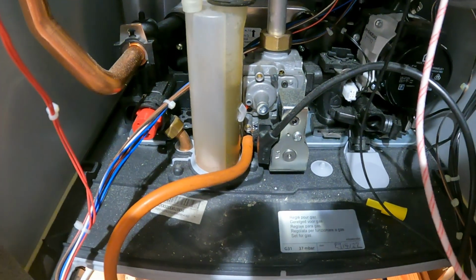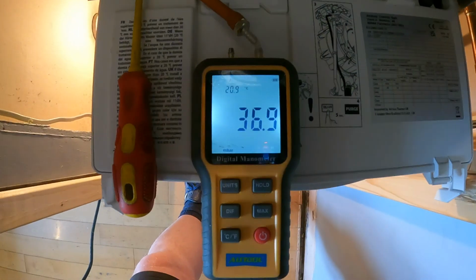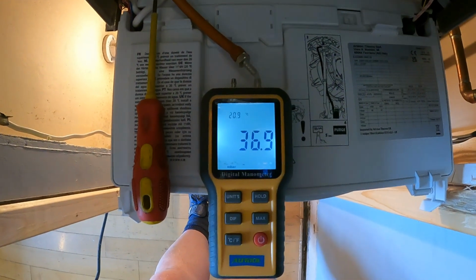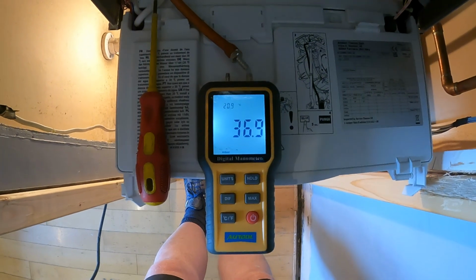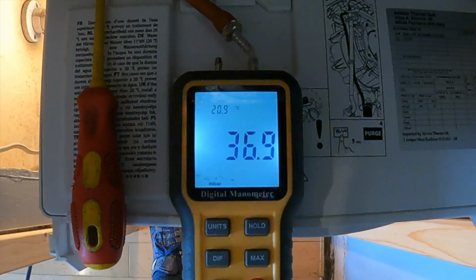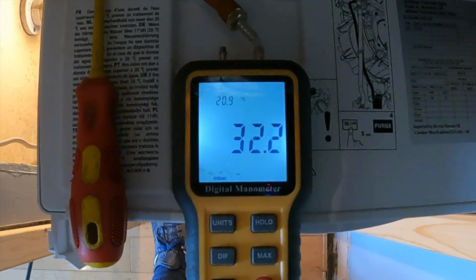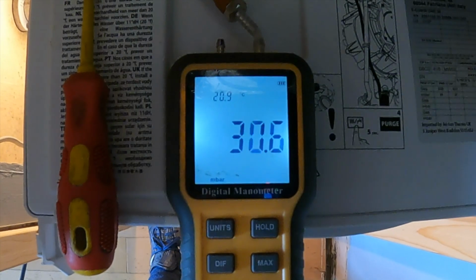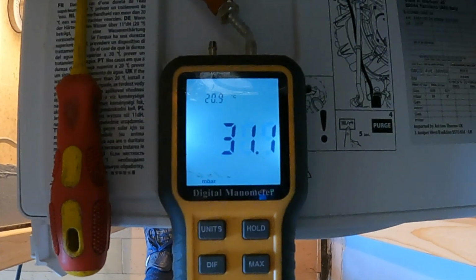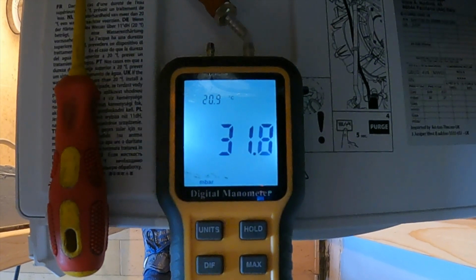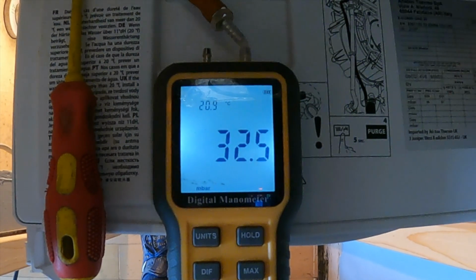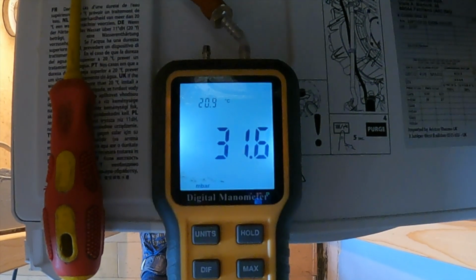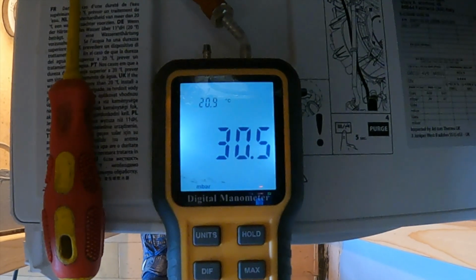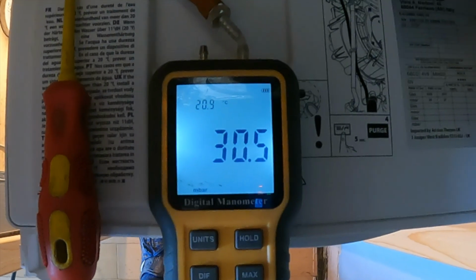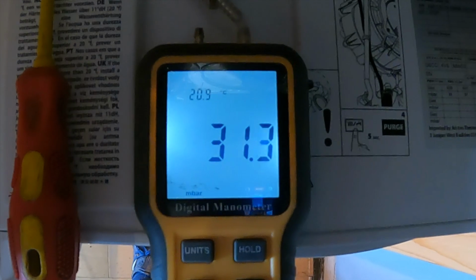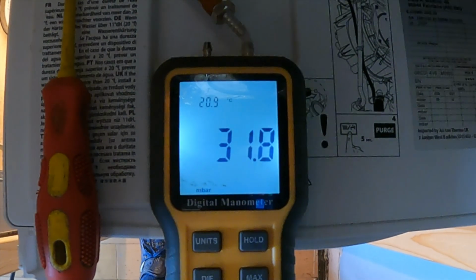So as you can see, we're connected at the inlet test point and we've got a standing pressure of 36.9 millibars at the test point of the gas valve. So we're just going to turn on the hot tap and see what it goes down to. So you can see we have a working pressure with the tap running of around 30 millibars.